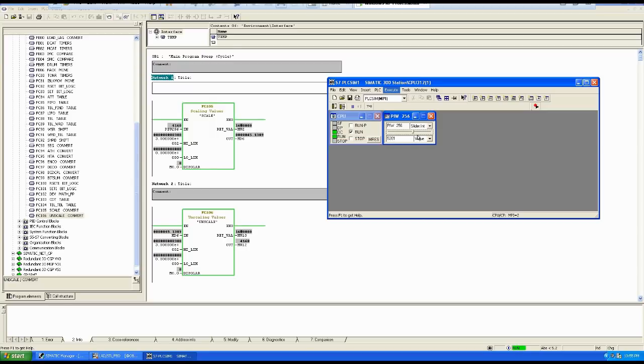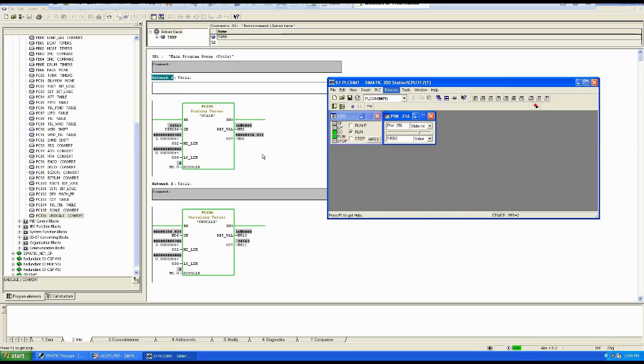Values are starting from 0. You can see we are getting the engineering value at the output. By engineering value I mean the actual value coming from the transmitter — the level between 0 and 300 that we discussed. So whatever the actual level value is, it comes here as the engineering value as the output of the scaling function. You can see 150 is the actual value coming from the instrument — that is the raw value at the input and at the output you are getting the engineering value. When you take a signal from the instrument you pass it through the scaling function. When you send a process parameter out as an analog signal to a final control element, you use the unscaling function.